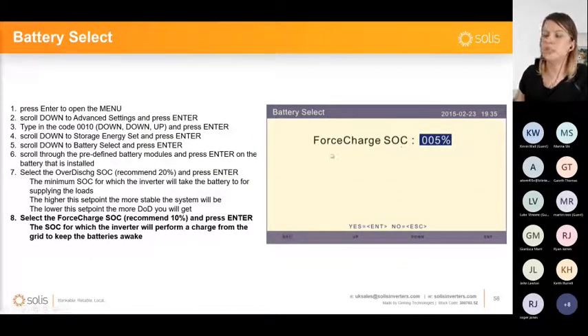This is a value that is being recommended by every battery manufacturer. For some it will be 5%, for some it will be 10%, or even 15%. Sometimes even if they say it's 5%, it's best to have it at least 10%. This is the default value that we are recommending, and you will find it already set up.